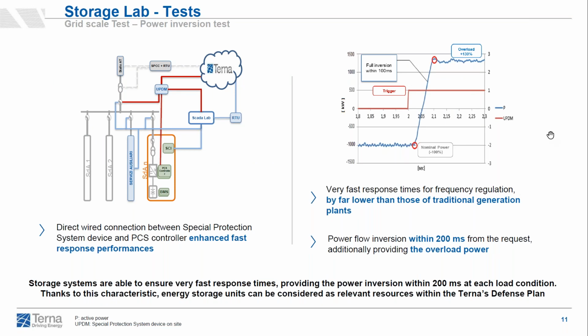Finally, I just want to show the results from a test made at grid scale level, which is the test of power inversion. This test has the objective to validate the capability of fast response of the ESS. Here on the right, we can see the results of one of these tests made on one of the ESS installed in the storage lab. In red, there is the trigger for a power request, while in blue we have the power provided. So the picture shows that the ESS is capable of power flow inversion within 100 milliseconds, additionally providing the maximum overload power.